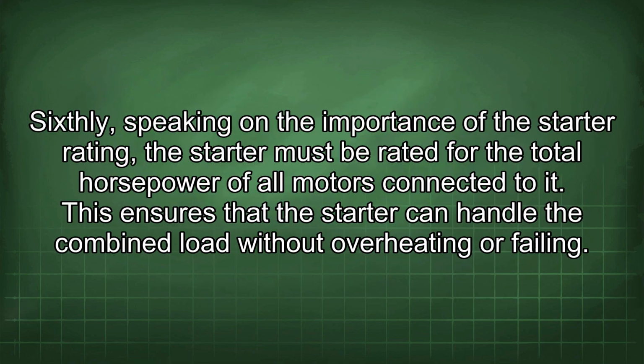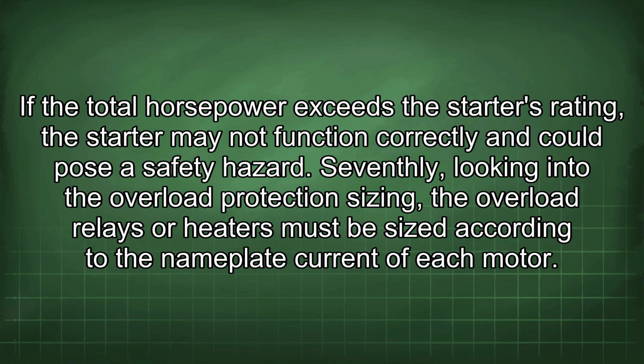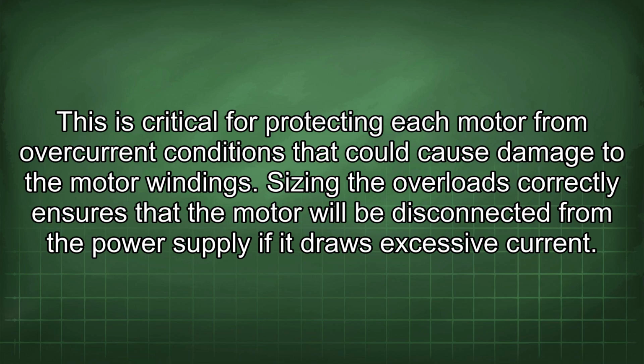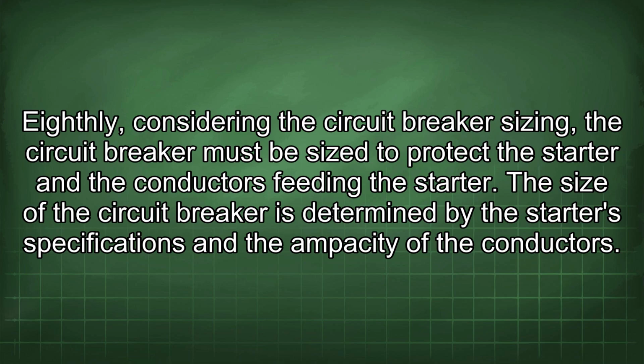Sixthly, speaking on the importance of the starter rating, the starter must be rated for the total horsepower of all motors connected to it. This ensures that the starter can handle the combined load without overheating or failing. If the total horsepower exceeds the starter's rating, the starter may not function correctly and could pose a safety hazard. Seventhly, looking into the overload protection sizing, the overload relays or heaters must be sized according to the nameplate current of each motor. This is critical for protecting each motor from overcurrent conditions that could cause damage to the motor windings. Sizing the overloads correctly ensures that the motor will be disconnected from the power supply if it draws excessive current. Eighthly, considering the circuit breaker sizing, the circuit breaker must be sized to protect the starter and the conductors feeding the starter.